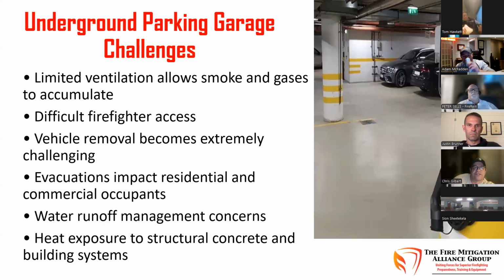Absolutely, the biggest thing we're pushing down here is exterior position only. We've seen so many incidents inside parking garages, and once you've got a fire in there, you're basically destroying that infrastructure—concrete spalling and all the rest. You've totally devastated the engineering specs for that structure. It's a massive issue if you have a fire underground. You can put as much water as you want on it, you're not going to put it out. You're just protecting exposures until it goes out, or you latch onto it and drag it out, which is the other go-to we've been doing down here in Florida.